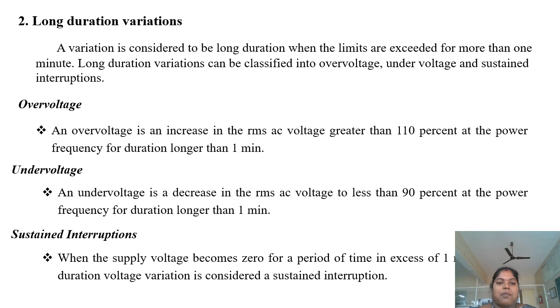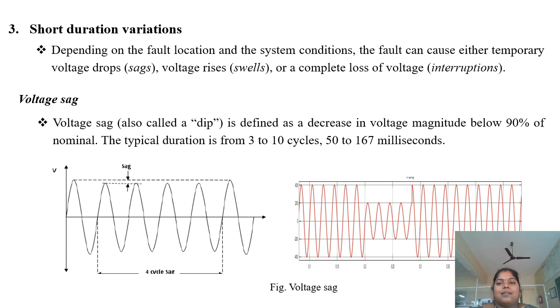Next one, short duration voltage variations. This is also nothing but RMS deviations at power frequency for less than 1 minute. It occurs due to faults, which can cause temporary voltage drops, that means sag, swell or interruptions. Voltage sag is nothing but a decrease in voltage magnitude below 90% of nominal. The duration is 3 to 10 cycles, that means 50 to 167 milliseconds.